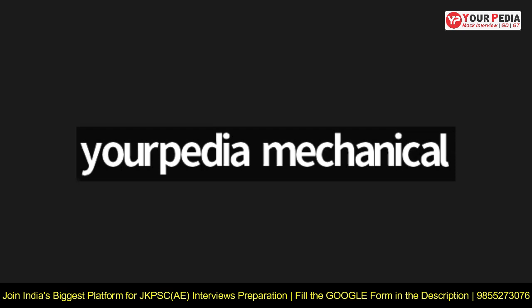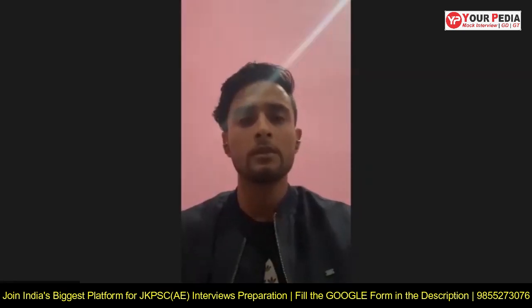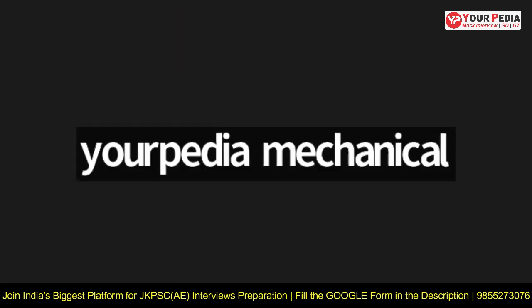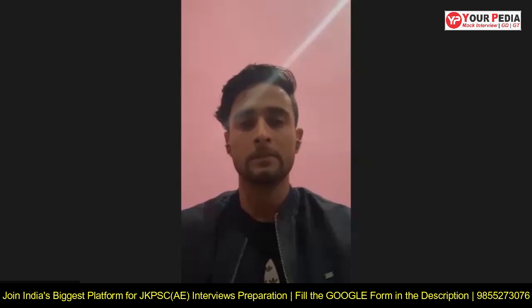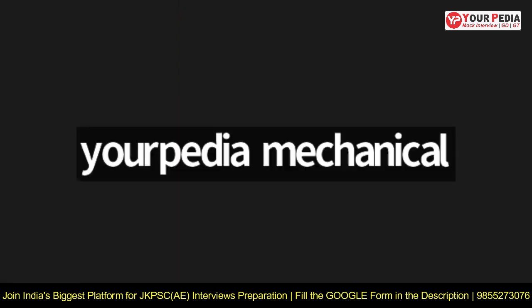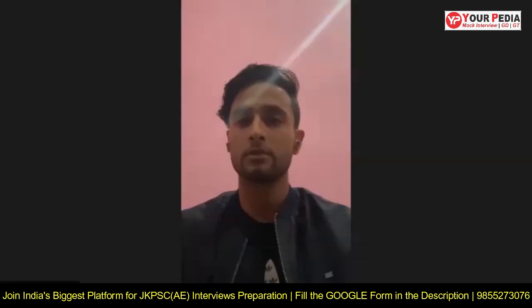Okay, sir. Steam jet refrigeration works on what? When we inject steam through a nozzle, the pressure drops, and that injection we carry out in a particular chamber, which increases the rate of evaporation of the water. The boiling takes place when the vapor pressure matches the external pressure. By carrying out the expansion of steam through a nozzle, we decrease the external pressure.